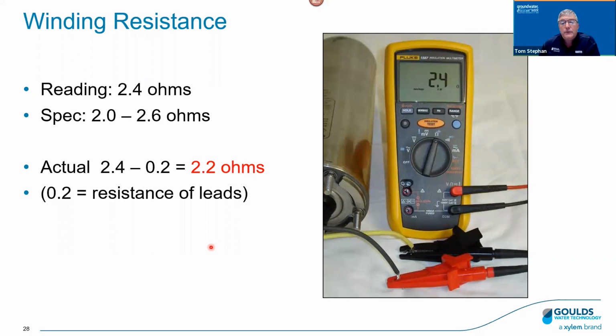VAR. So R is your line to line. I personally try to keep this straight by line to line versus line to ground. So winding resistance, we can see here in the picture, we're measuring line to line. This is something that needs to be looked up in the main manual or the service manual, and there is a spec. For example, here my spec is from 2 to 2.6 ohms.